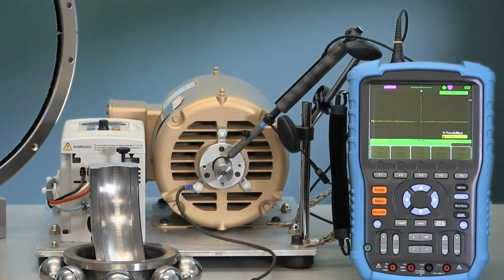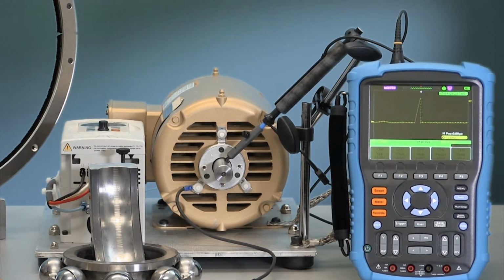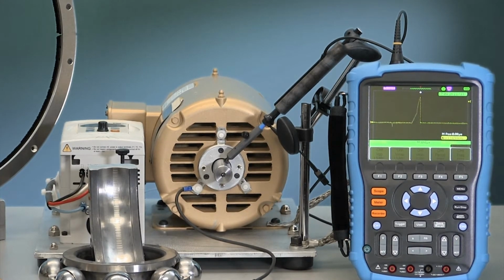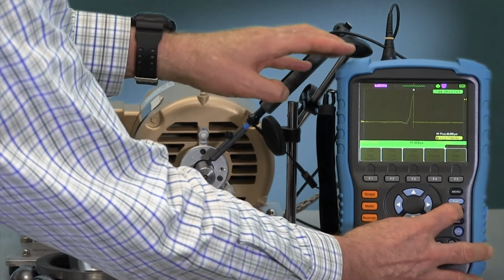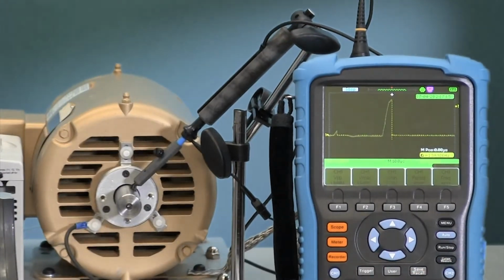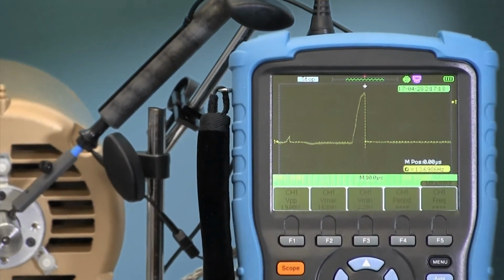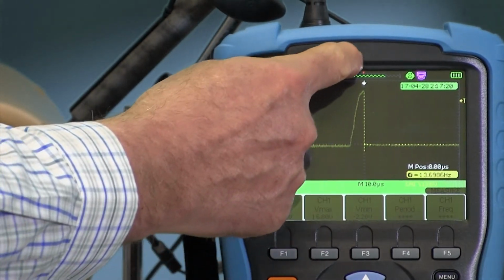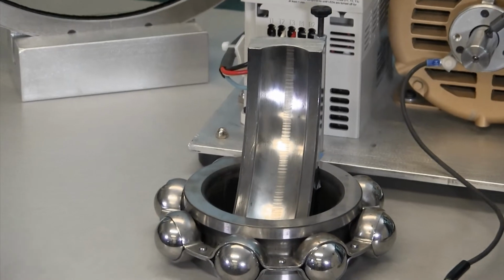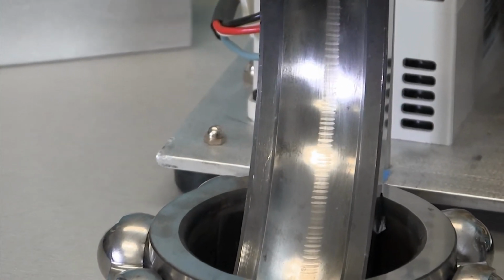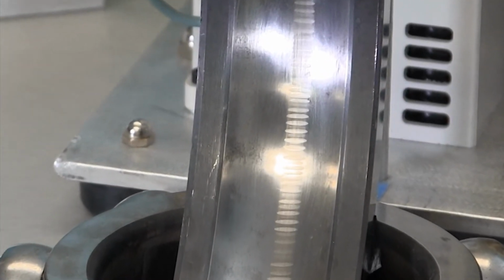So when you look at the oscilloscope, you can see continuous bearing discharges in the waveform, and that's that slow increase with very sharp negative going discharge that you see. Now I'm going to freeze the screen so that you can see what's going on a little bit closer. And you can see that voltage increasing slowly and a very sharp discharge. That's a pit being created in the bearing race, which eventually can cause fluting damage and failure of the motor.